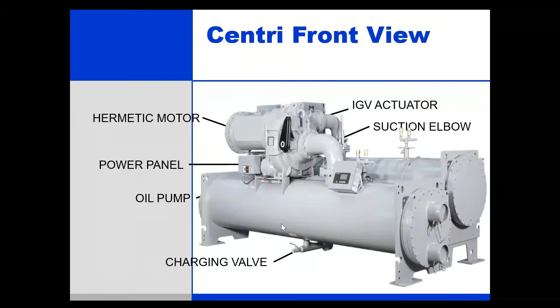Now, the oil pump is the most critical component in a centrifugal chiller, because the oil pump pumps oil into the bearing and lubricates the bearing. And as we know, the centrifugal chiller operates at a very high RPM. It is very important that the bearings are properly lubricated and the oil is maintained at a certain viscosity. You have at the bottom the charging valve. Generally, if you have to do any side charging, you have to do this.